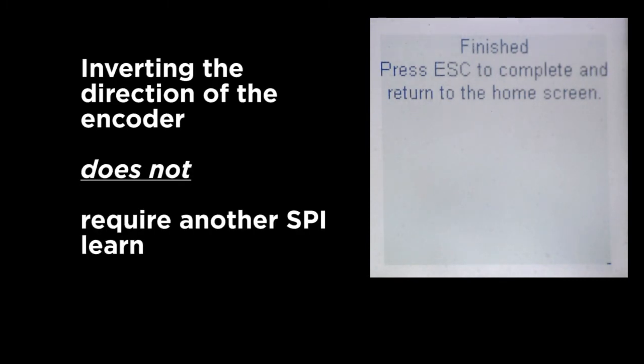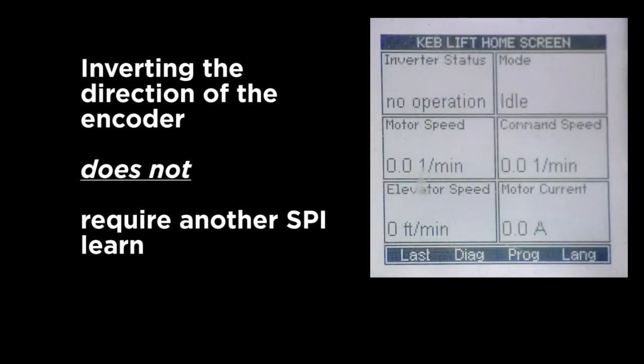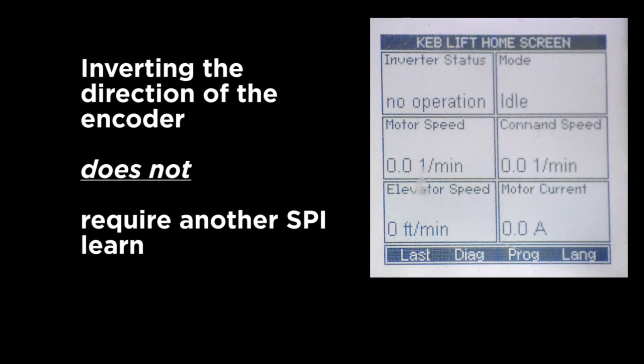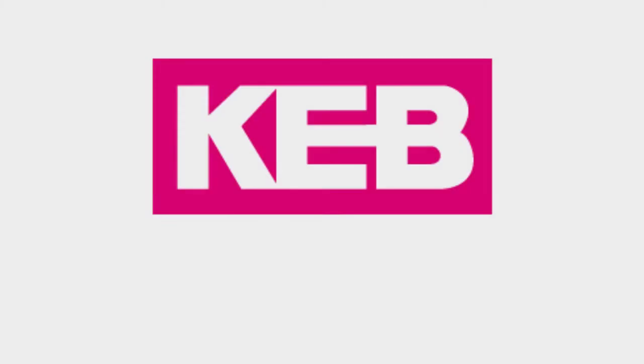Finally, it'll ask if it traveled in the correct direction. If you gave it the up direction and it went down, you could hit no and it would invert the direction of rotation. Or if you hit yes, it just keeps the setting as is, and that refers to the LE parameter where we had inverted or swapped the phases for the encoder. That same parameter can be used to invert the direction of rotation.